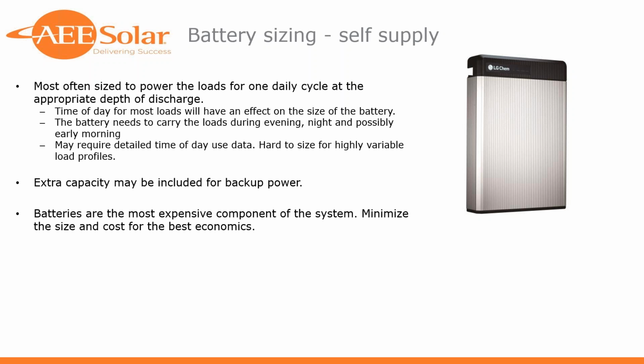And it's going to make a difference what the load profile is of the site that you're designing this for. If the loads are mostly during the day, the solar may be a good match for them. If the loads are more typically residential loads where the majority of the load is in the evening or in the early morning, then you do need to size the battery to handle the loads during those periods when there's not so much sun, especially if the utility is not allowing you to bank any power from the sun in the middle of the day, or the time of use is making it not economical to do so.